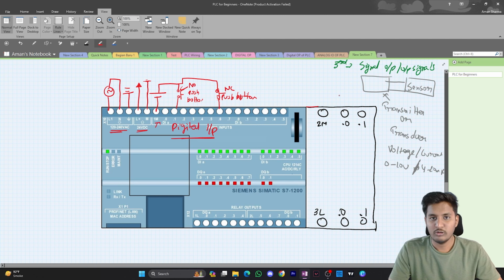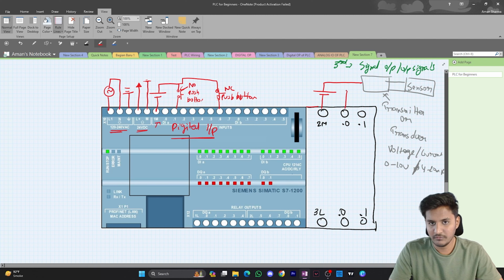As I told you, we are going to use sinking type all over our PLC. So we will make the common as a sinking type and we'll connect the output from the sensor transmitter to our PLC. So now our input supply is clear, our output DC supply is clear, our digital input is clear, and our analog input is also clear.